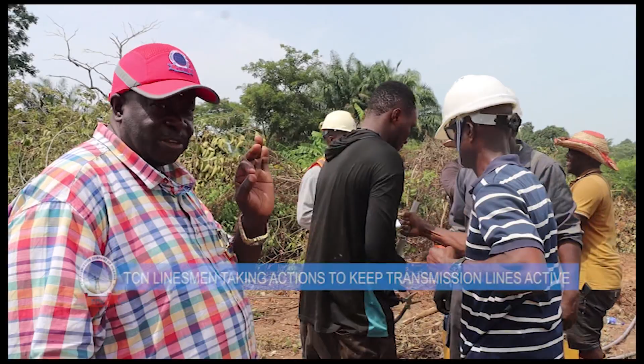The process they are about to carry out now is joining of the broken conductor line. After compressing it, we now wear in another aluminum cylinder. As you can see here, there are layers of aluminum being cut — we have three layers of aluminum before the steel.